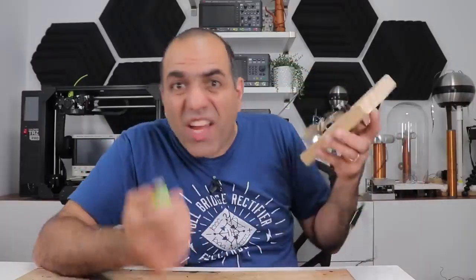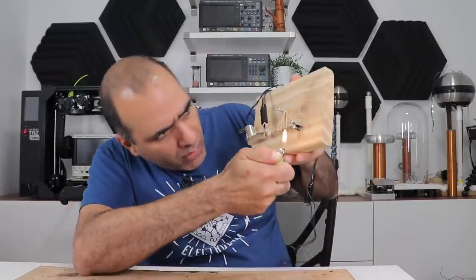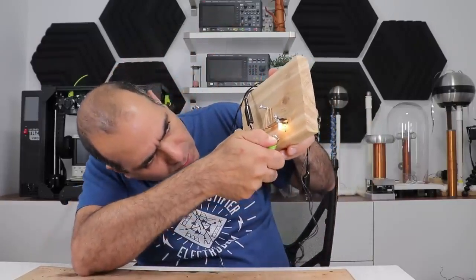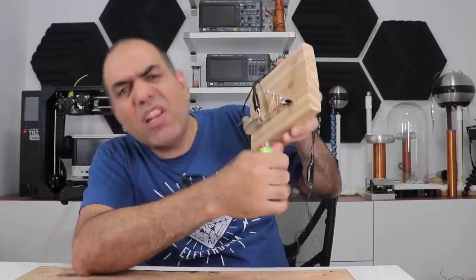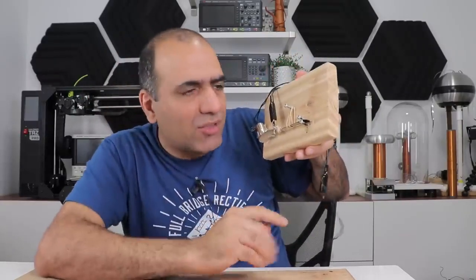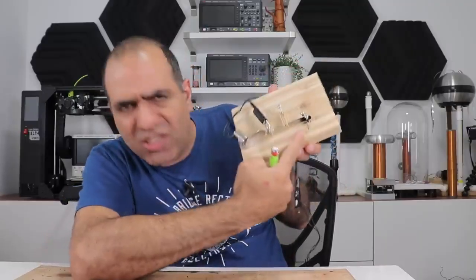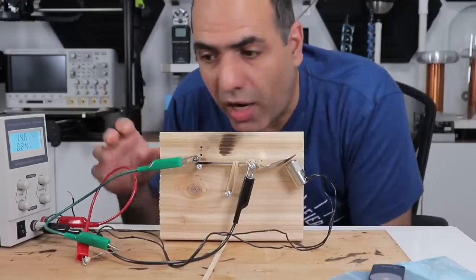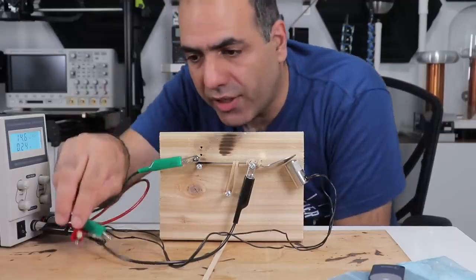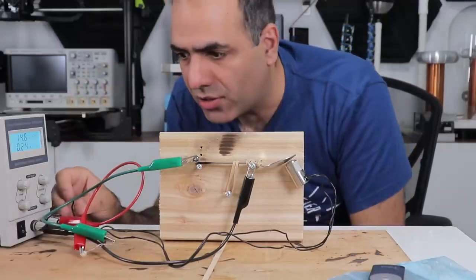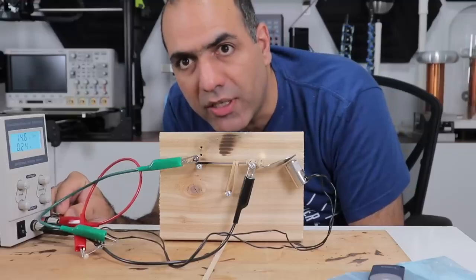And that's not all. For some weak and small relays, there needs to be a minimum contact voltage and current present. Like when you switch them, there is a recommended minimum load for reliable switching. Why is that, you ask? Let me show you. If you don't use your relay for long periods, there can be a very thin layer of oxide on the contacts that don't let it connect well, or in my case, it's soot. Soot. Here I'm trying to turn on a low voltage LED circuit, and because the contacts are covered in soot, it won't turn on, see?